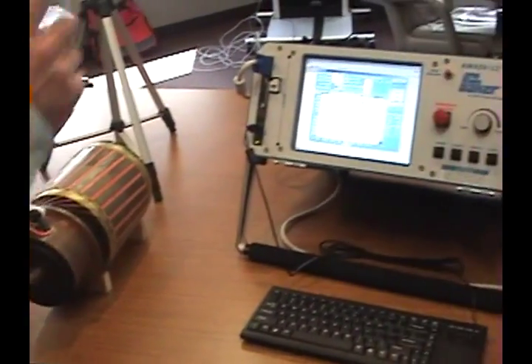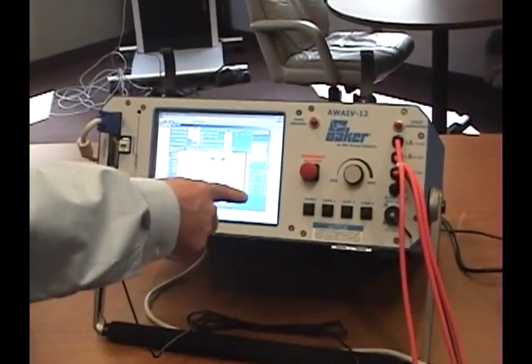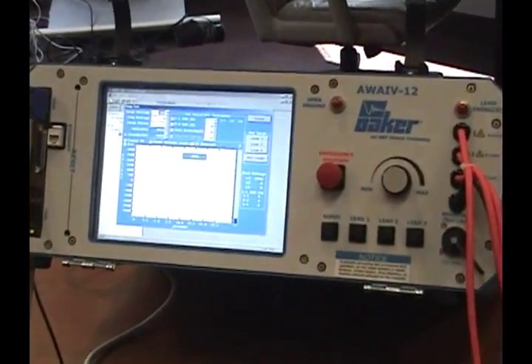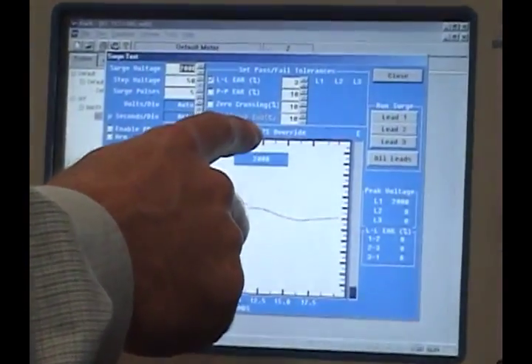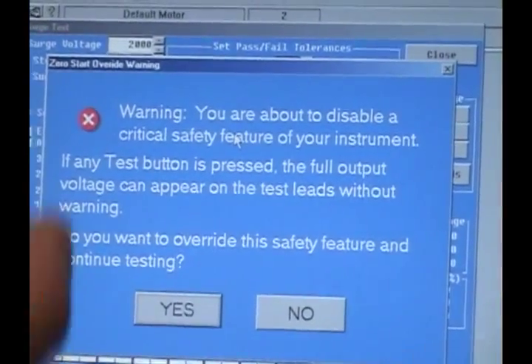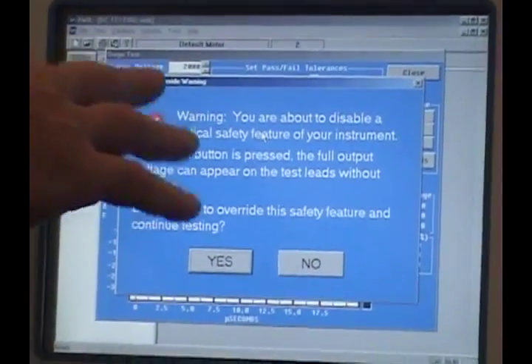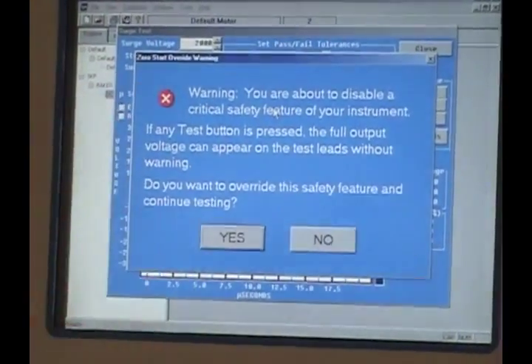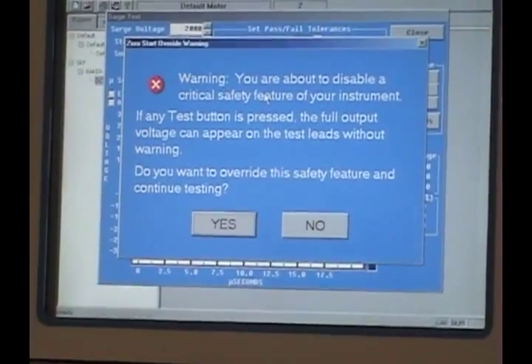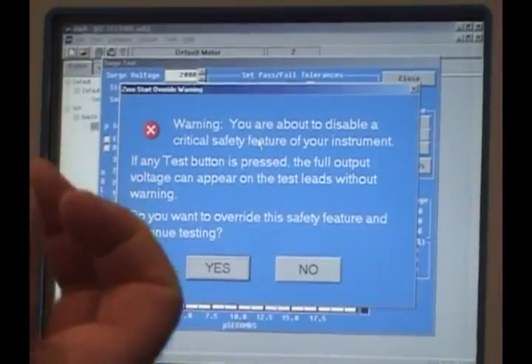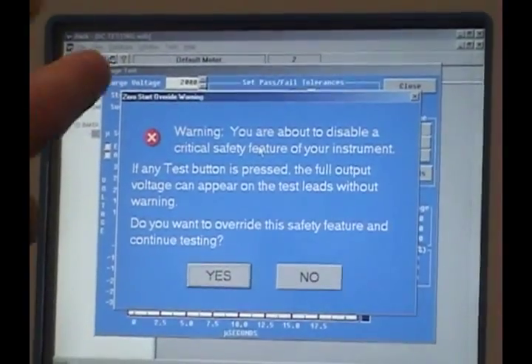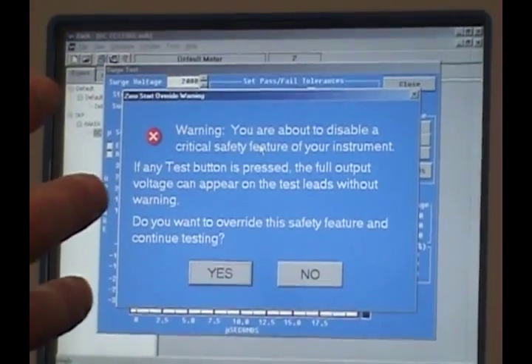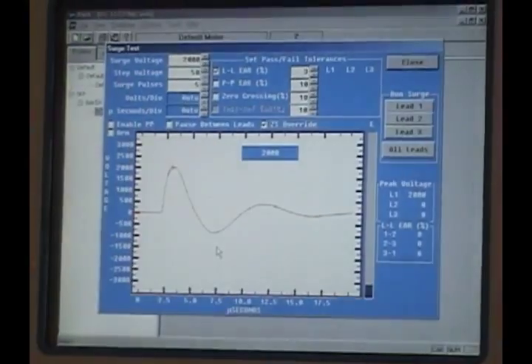This time, we don't press lead one. Let me back up a second. We need to press the zero start interlock override which brings up a warning saying that you are removing the zero start interlock. So whenever you press the button, you will automatically receive the voltage that you set. In this case, we set it at 2,000 volts. So I am going to say yes, I agree to that.